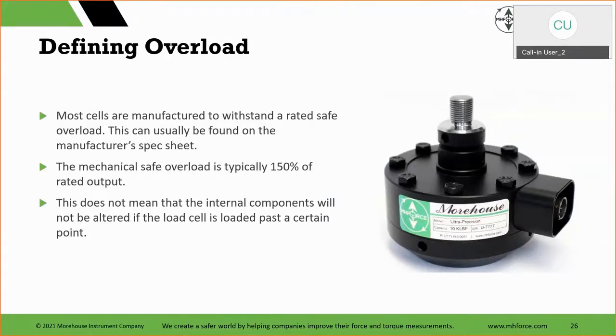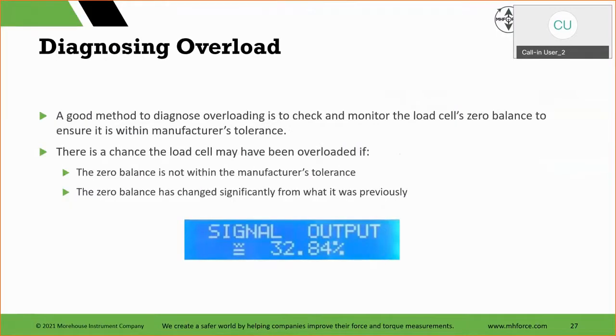Most cells are manufactured to withstand a rated safe overload. It's usually found on the manufacturer's spec sheet. On our load cells, the safe overload for most of them is 150% of rated output. Some are higher, some are less. You have to check the spec sheet. That does not mean internal components will not be altered if the load cell is loaded past a certain point. A good method to diagnose overloading is to check the load cell's zero balance to ensure it's within the manufacturer's tolerance. That tolerance is typically less than 1%. There's a chance a load cell may be overloaded if the zero balance is not within the manufacturer's tolerance and has changed significantly from what it was previously.